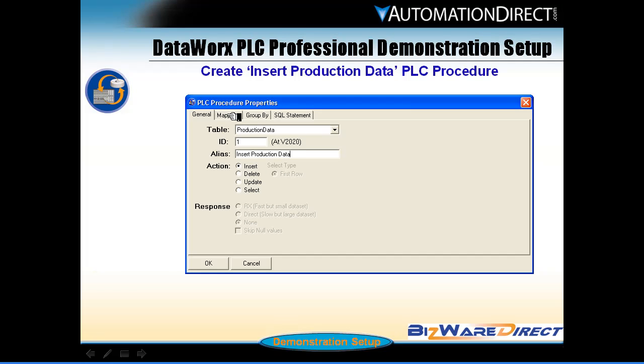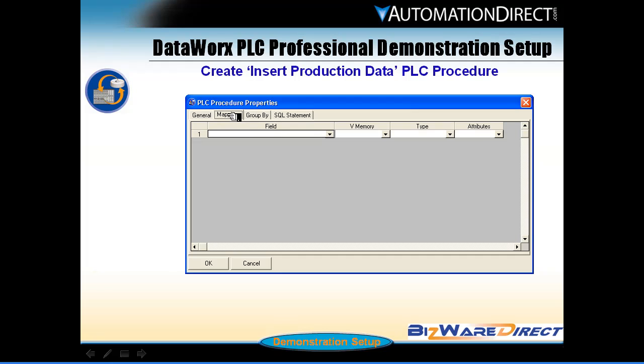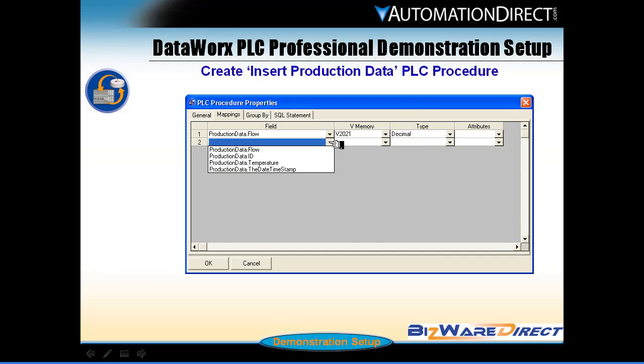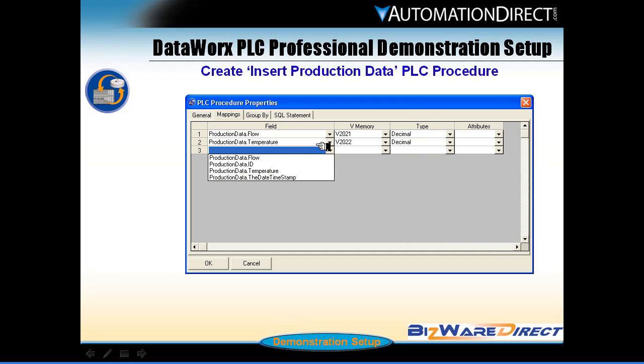Choose the Mappings tab. Here we will create a mapping between the vMemory source location in the PLC and the destination field in the database table. We will populate flow based on vMemory location 2021. The data type is decimal. Create a similar mapping for temperature. The PLC will only populate the flow and temperature fields. As we reviewed earlier in the database structure, the ID and the date timestamp fields are both defined in the table structure itself and are automatically assigned values when a record is added to the table. Click OK.